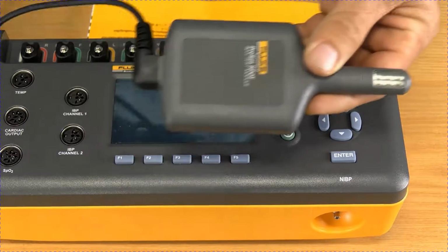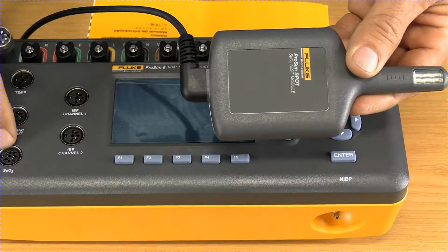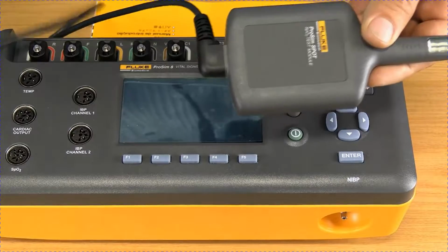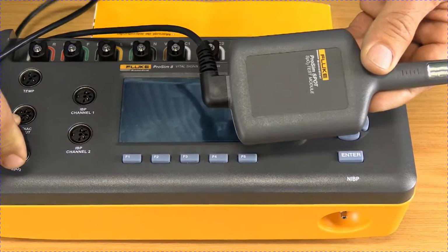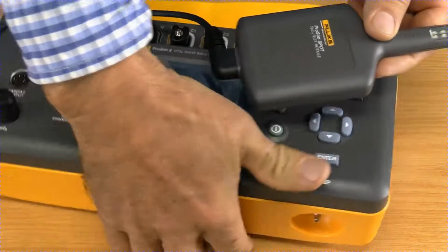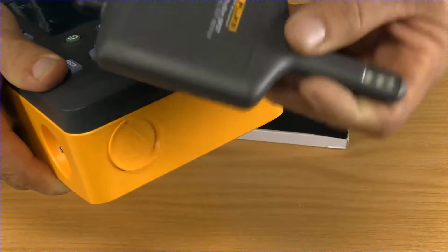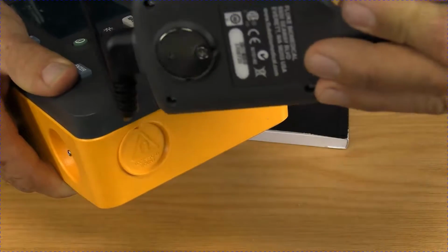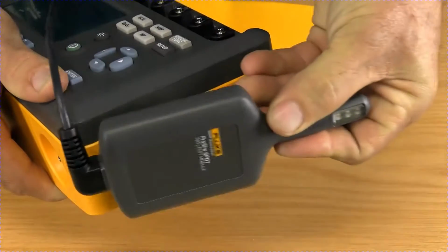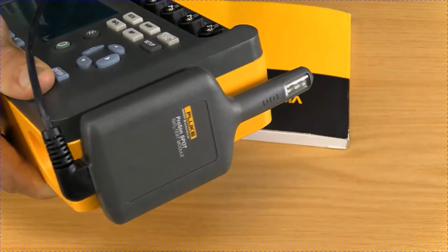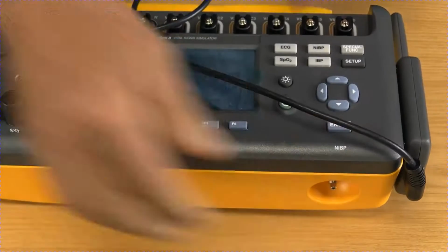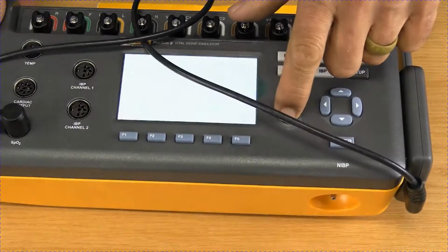You'll see that on the ProSim 8, we have a connector here for SpO2. If I move it a little bit that way, you can see that. This cable just plugs in there. And then on the side of the ProSim 8, there's a little magnet, and you've got a magnet on the back of the simulator, or the finger, which is just a nice storing place for it.